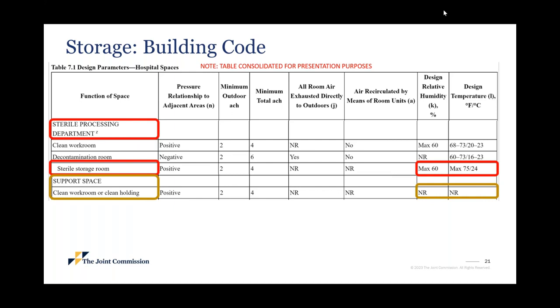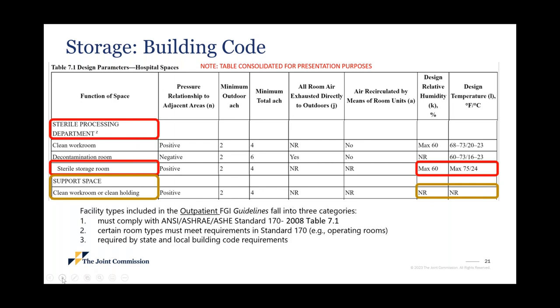But look at the support space, that's the part in mustard. If you are putting your sterile supplies into your support space, into a clean workroom or clean holding, then that room needs to be at positive pressure, but there is no design humidity requirement and no design temperature requirement. So in those cases, we would not require that your organization monitor the temperature and humidity. Very important, again, to know where the requirement is and why it is a requirement.